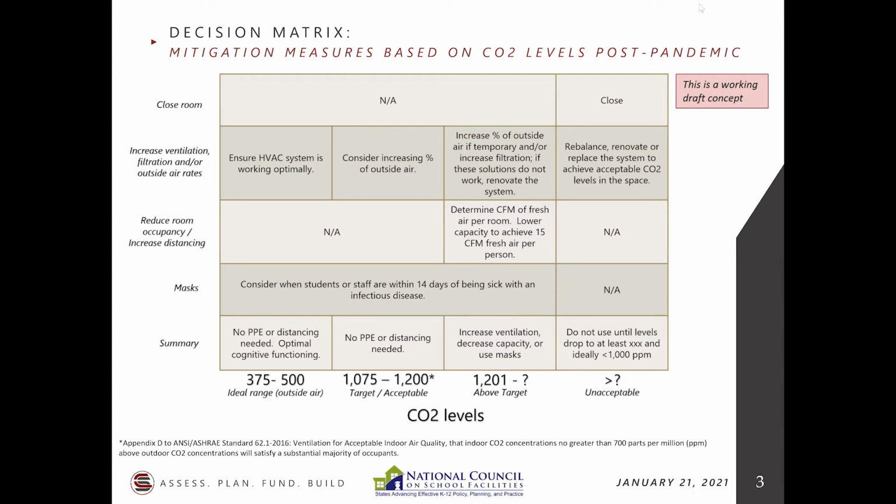Well, 15 cubic feet per minute per person. It's about 13 to 15 when you look at ASHRAE standards. It falls into that as a minimum. And the levels of CO2, you can of course calculate how many CFM per person you're getting.